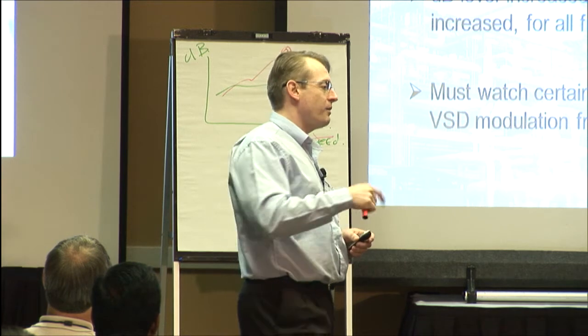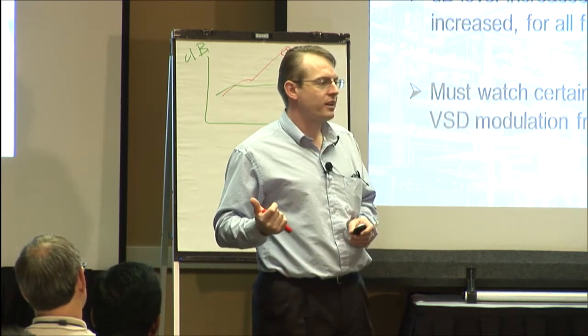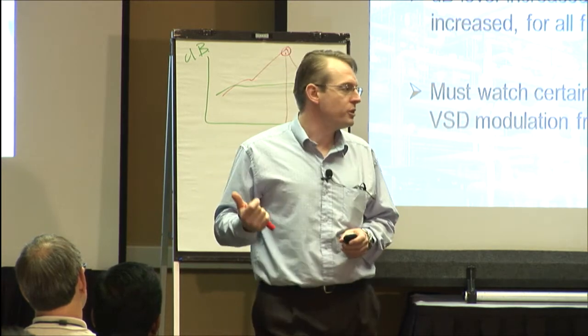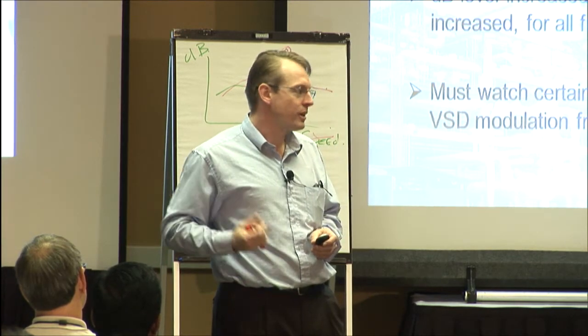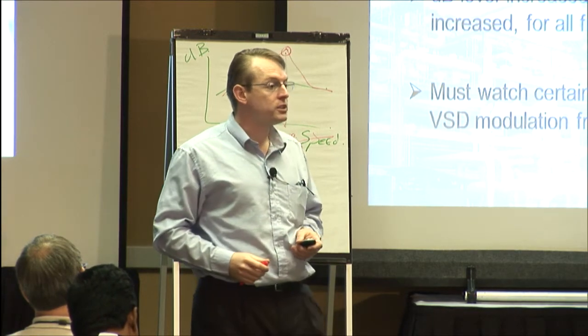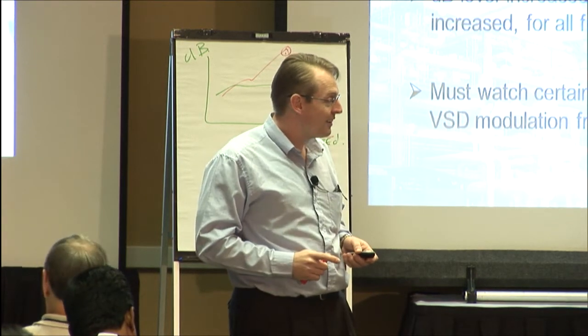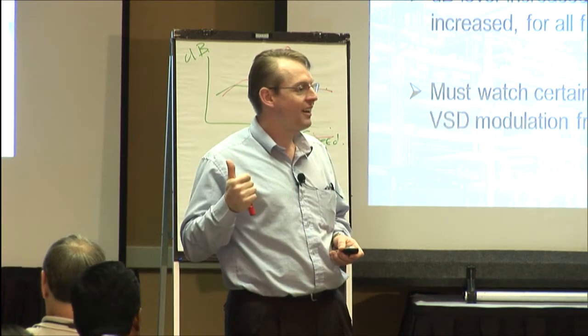Because lower, we're going to get potentially better resolution. The higher we go, the less we're going to get. The higher the frequency, the more attenuation. Okay, so we're looking for a good signal here. Now, occasionally, if you've got a lot of background noise, okay, what might you do? Go higher. Why?